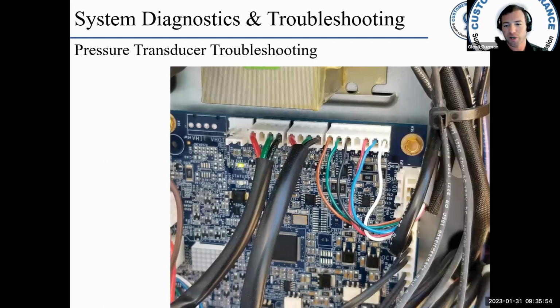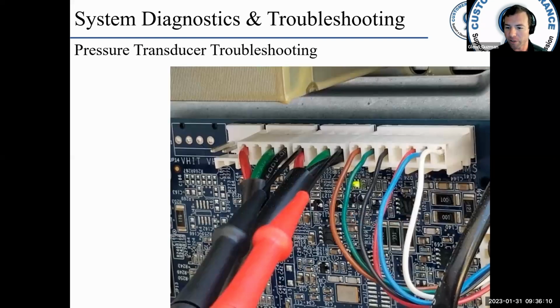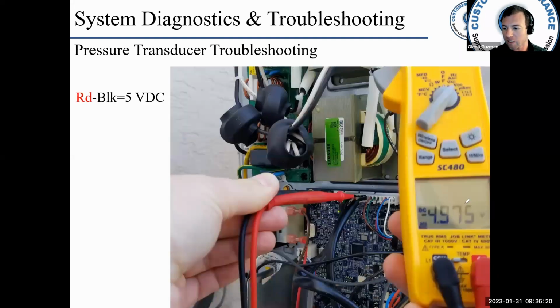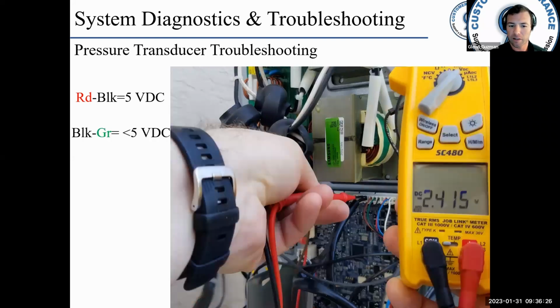Troubleshooting, allow some variance, but they should be reasonably close. Like I said, red to black is power to the transducer. Black to green is your voltage coming back. So you can use your thin meter leads and get in behind the plug while it's connected. You see here red and black, you should have 5 volts DC. We can read 4.9 on the meter. And then something less than 5 volts DC coming back between black and green.